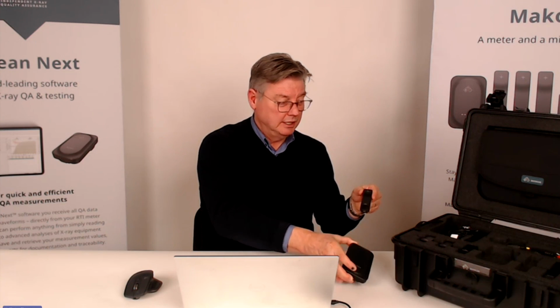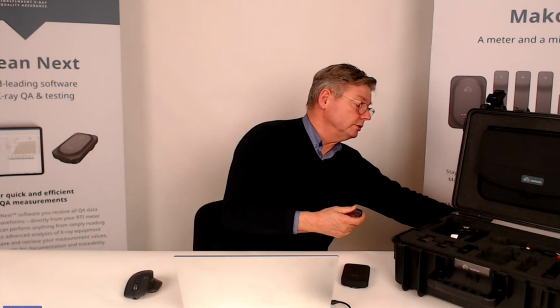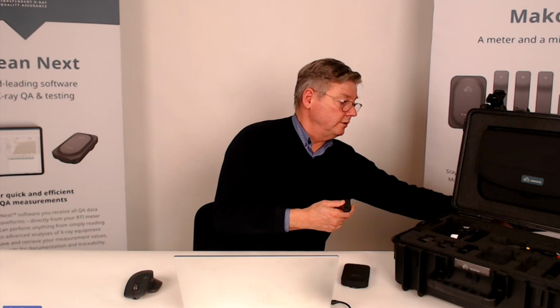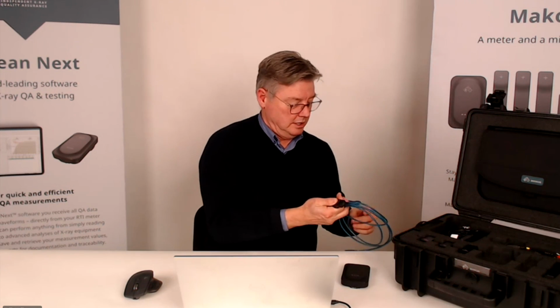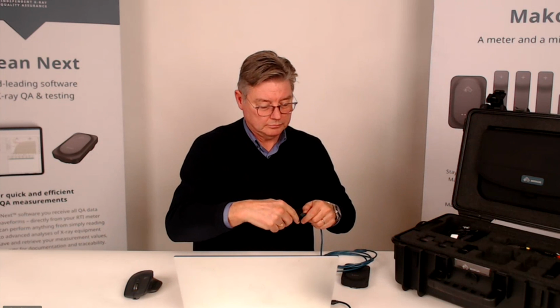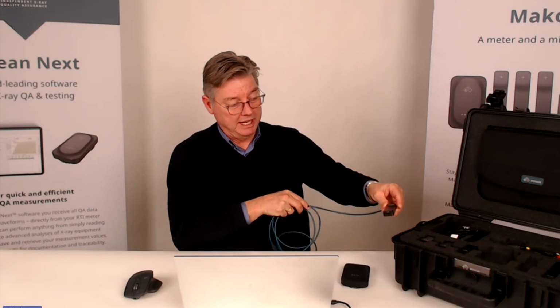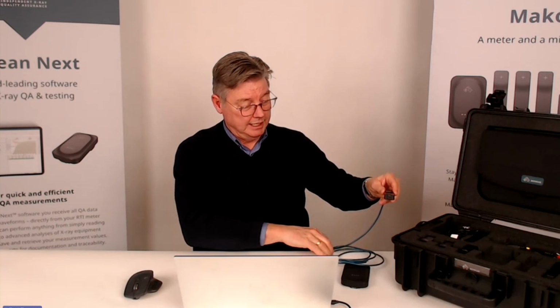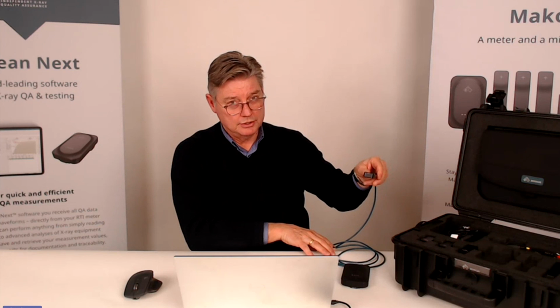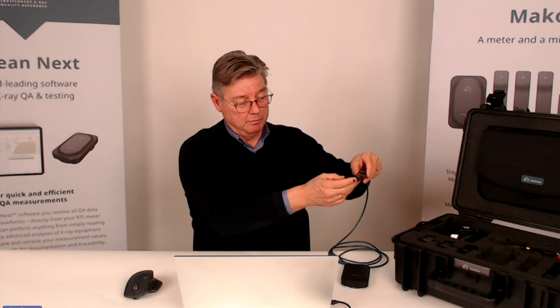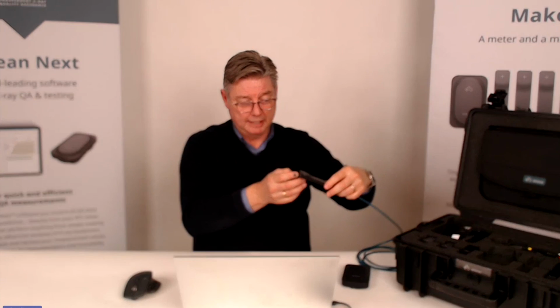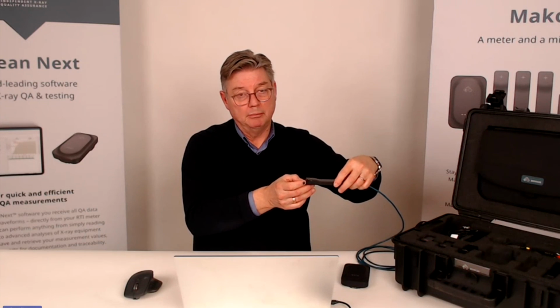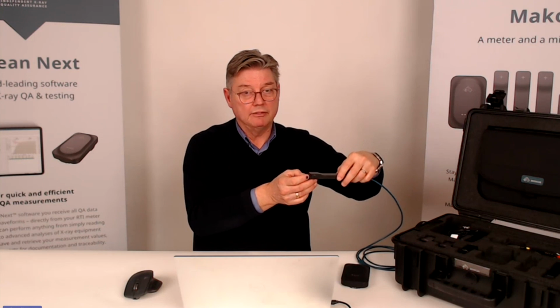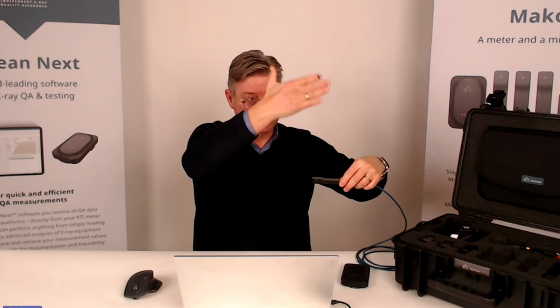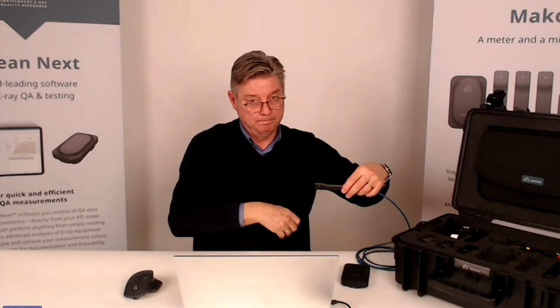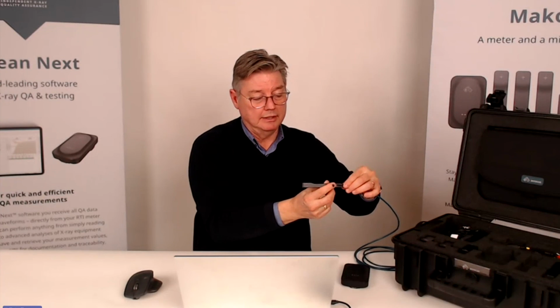And putting it on the couch, we can have it connected like this. If we put it into the gantry, I would suggest that we use the cable so that we have a better placement in the gantry for it. And again, we have a very good angular tolerance. So even if we're placing it a little bit like this in the beam or a little bit like that in the beam, the effect is going to be minimal when it comes to the measurements. As long as we're in this direction when the beam comes like so. So yeah, I'd do it like this in the CT with the cable connected.